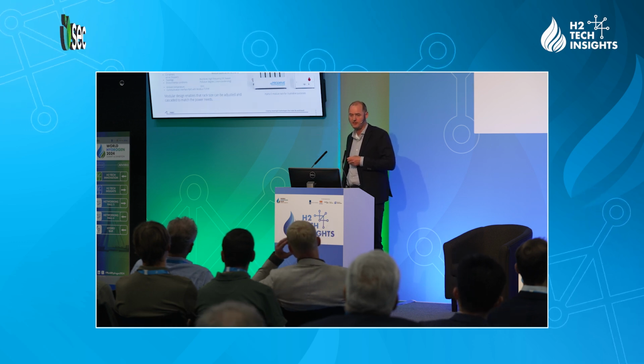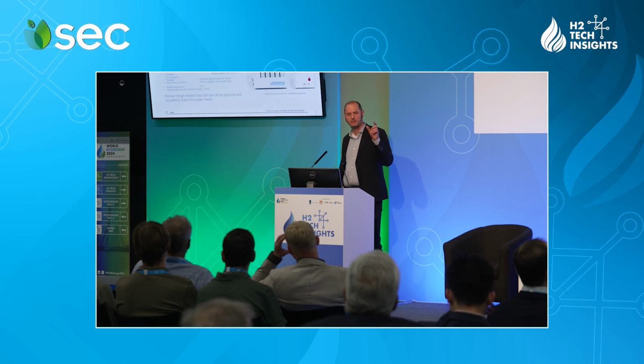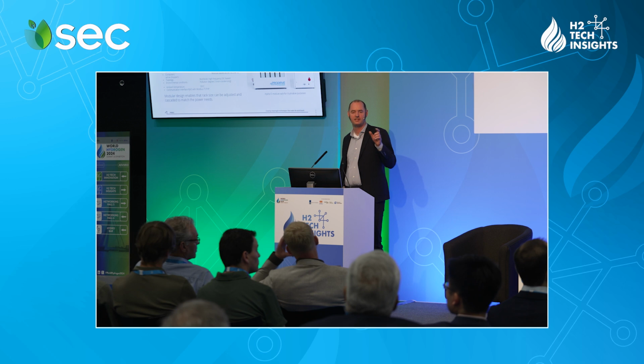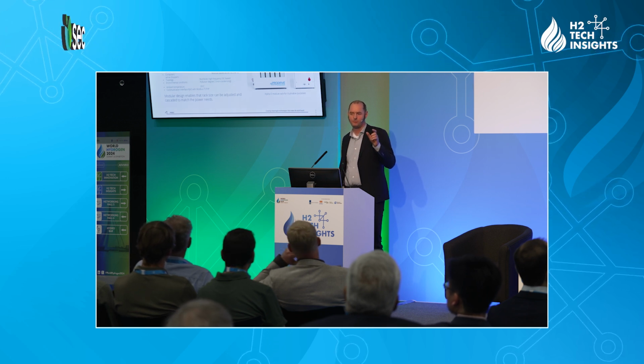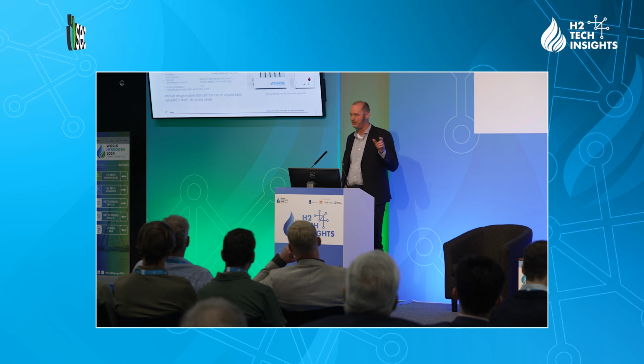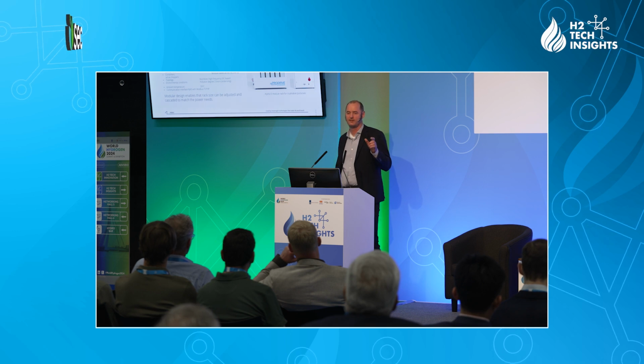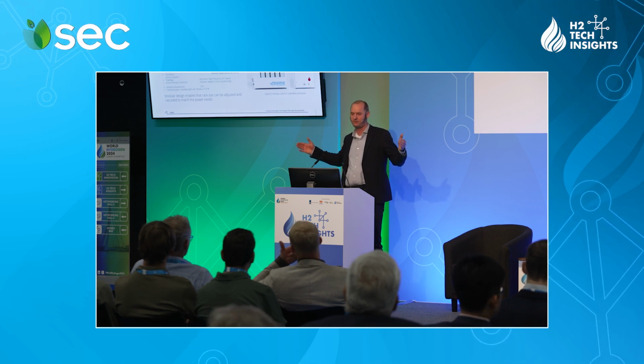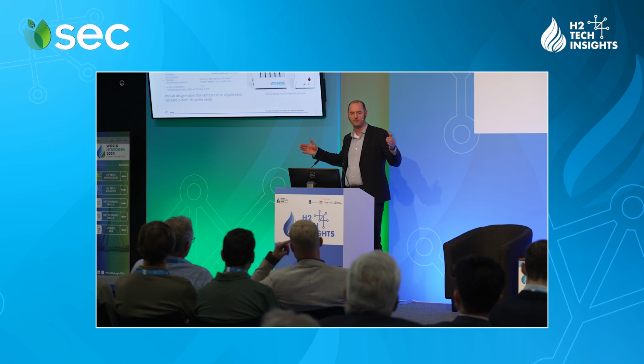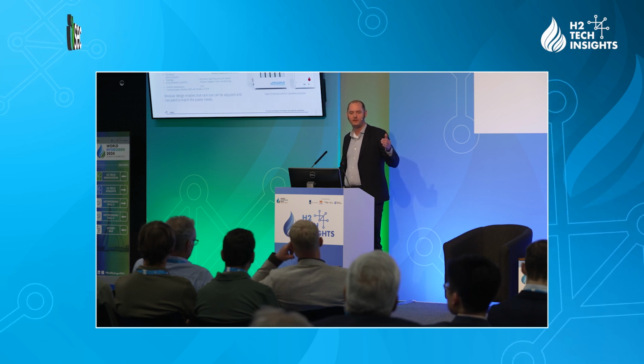And finally, the fact that we are switching so fast means you can switch off and switch on modules as your load is increasing or decreasing. And that basically means that you can always work at your optimal conversion point. So the efficiency that you see here, a peak efficiency of 98.7% over almost a complete load range from 5 to 100%, remains more or less at that very high efficiency. And that is definitely a difference from the older technologies that I haven't seen out there yet.